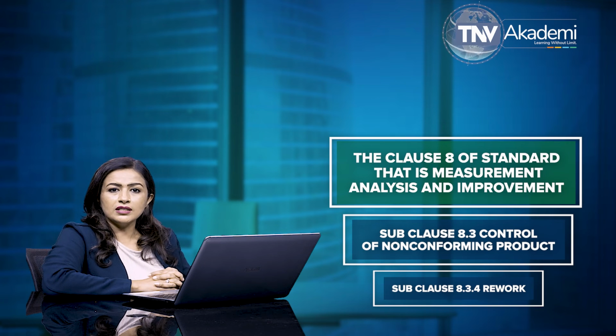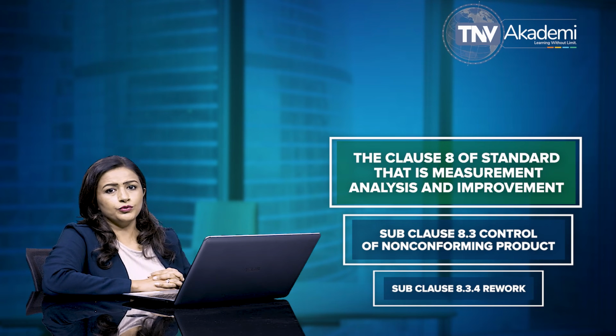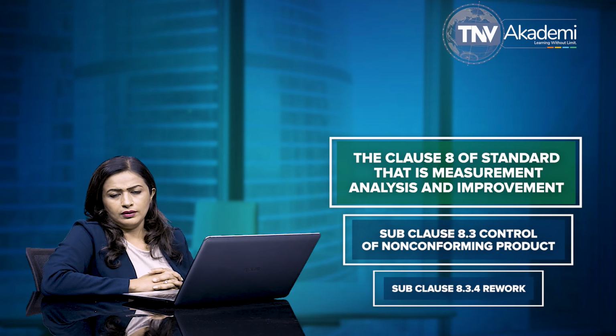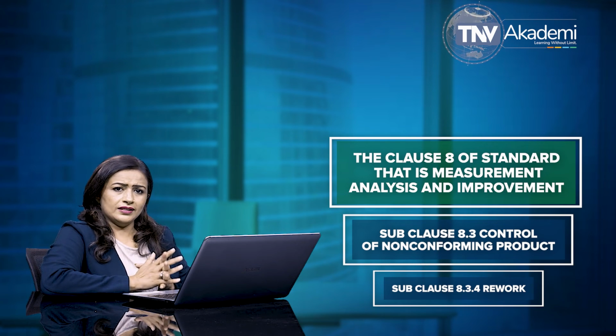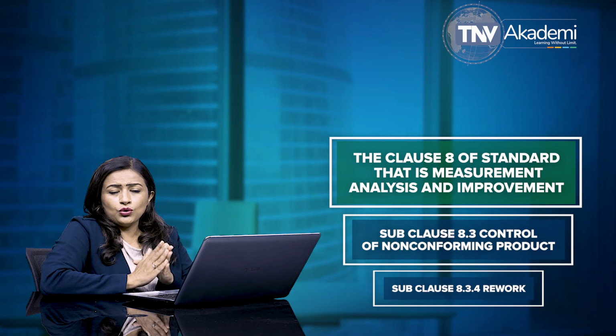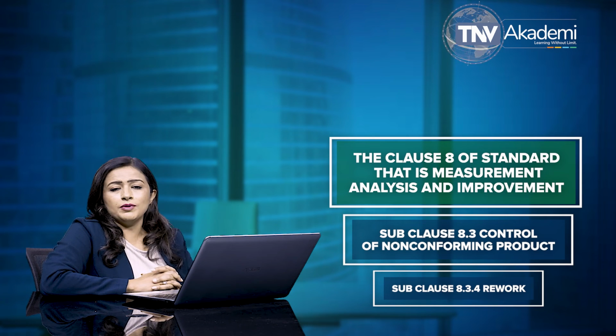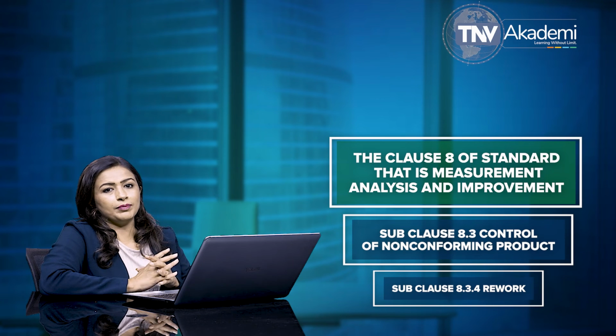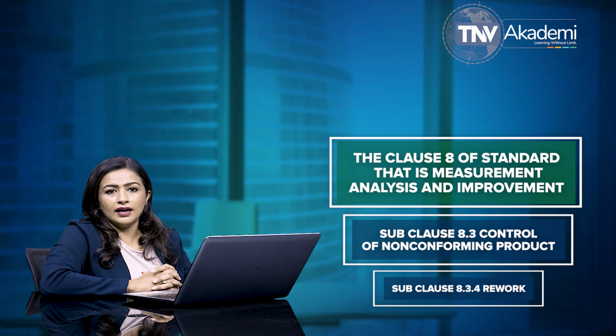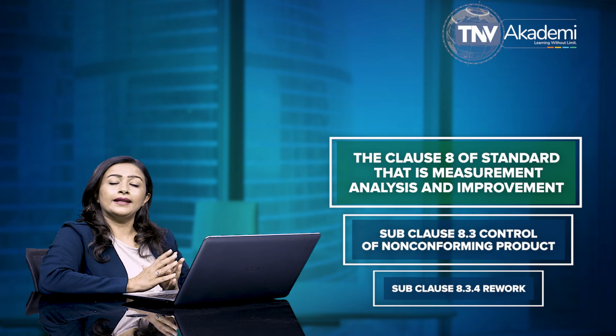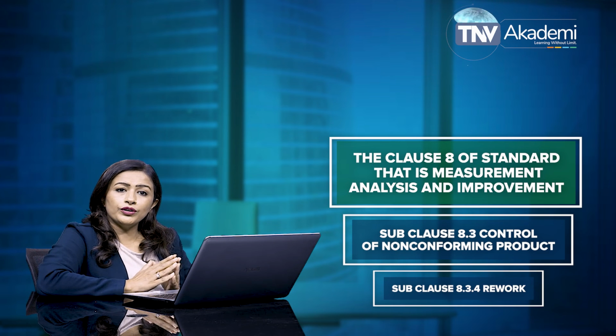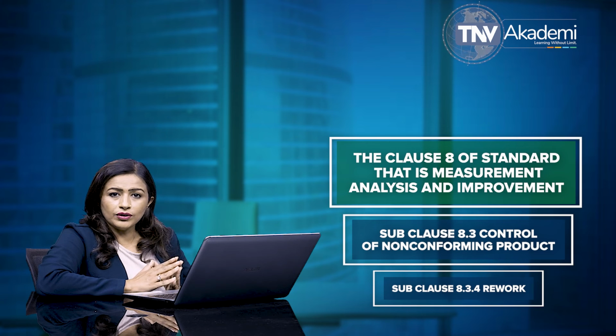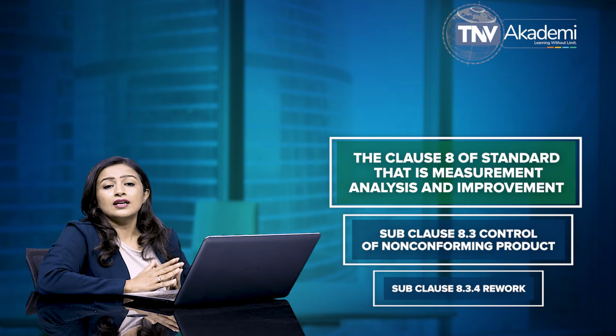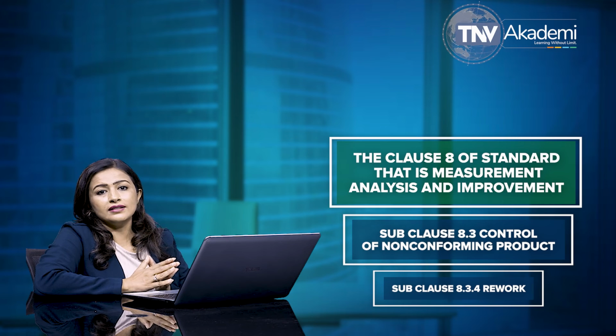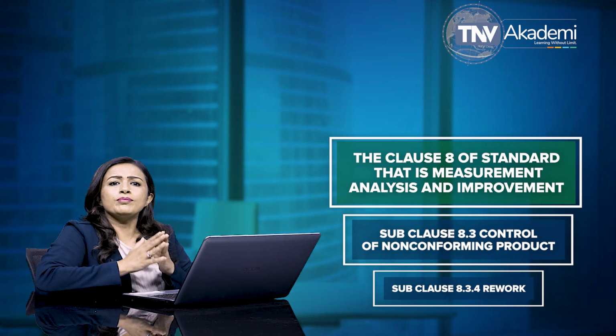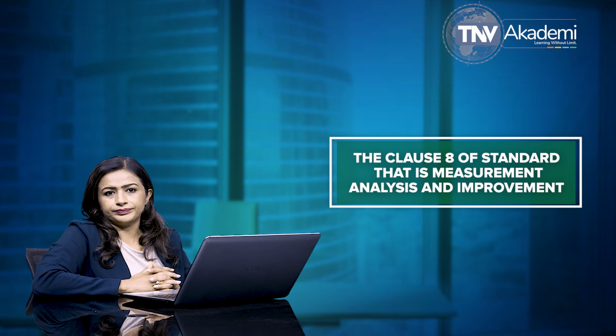These procedures must undergo the same review and approval as the original procedure. Clause 8.3.4 states that after the completion of the rework, product must be verified to ensure that it meets applicable acceptance criteria and regulatory requirements. Lastly, subclause 8.3.4 of ISO 13485 specifies that the organization is required to maintain the records of rework to meet the requirements of this standard.